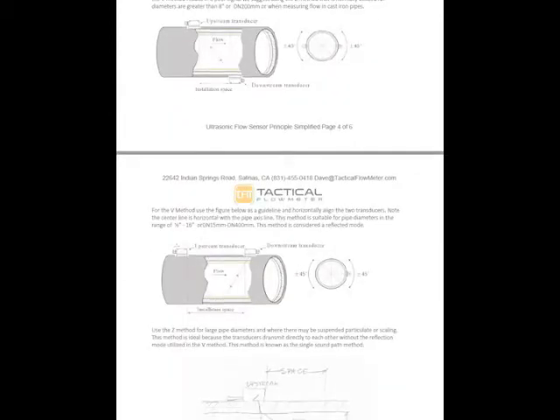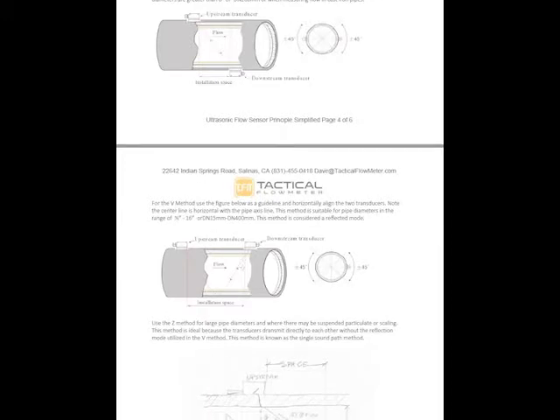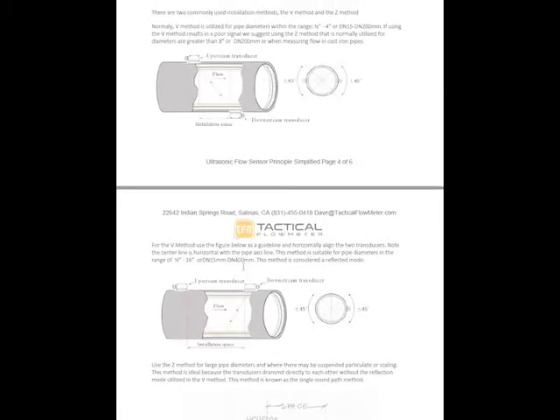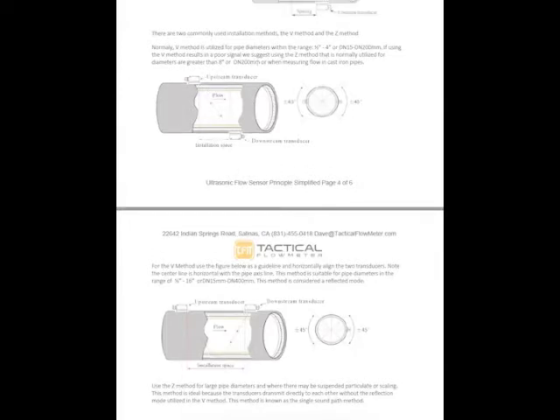we want to show the 2 different methods. This is the most common method we will suggest that folks use, from 1/2 inch to 16-inch pipes, most commonly used. And then this explains why you would use this kind of system. If the signal's poor, or you're measuring the flow in greater than 8-inch, or measuring flow in cast iron pipes, you would be using this kind of direct shot, not a ricochet like this, but the direct shot.